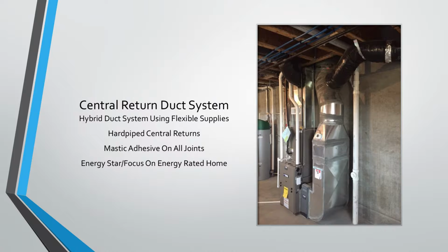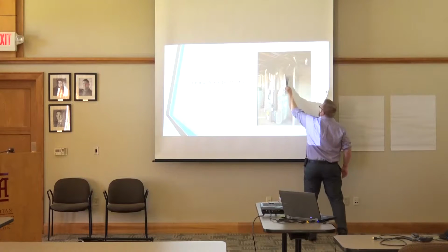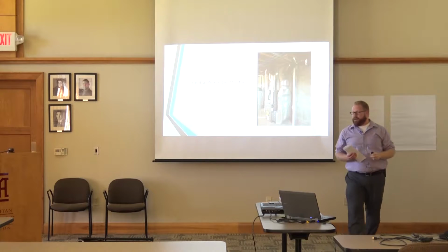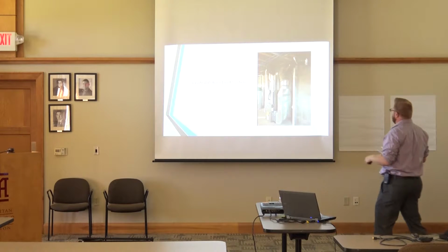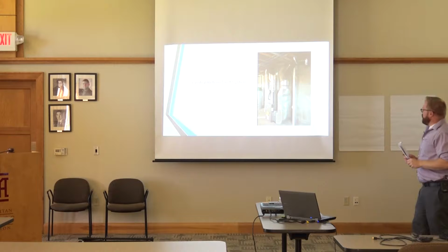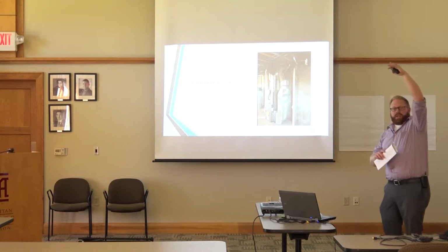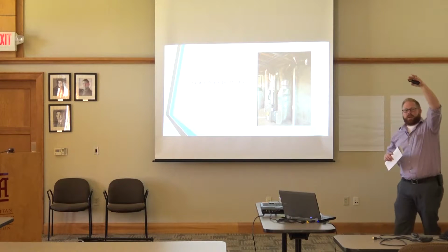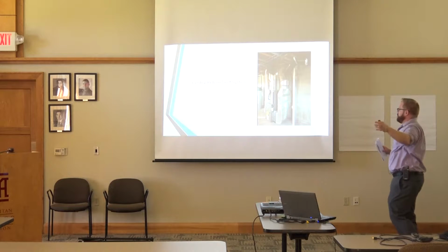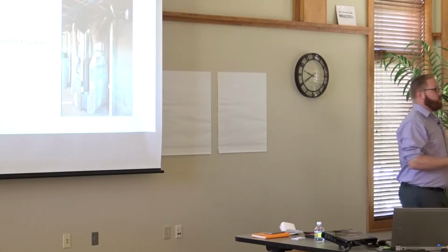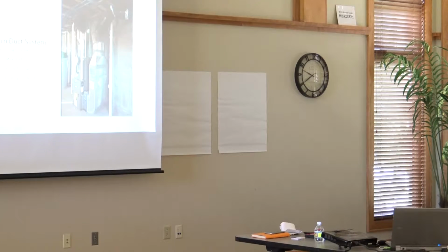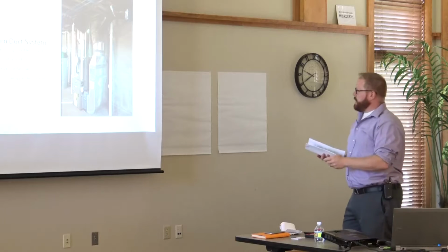One other thing you'll notice is the actual fresh air makeup right here. It's coming into the side of the return. So our makeup air is 5 feet from the blower, and we're also 5 feet from that first connection to the return. So we're not worried about dumping that cold air that's pulled in from outside, having that come back through the grill so you actually feel that temperature difference.